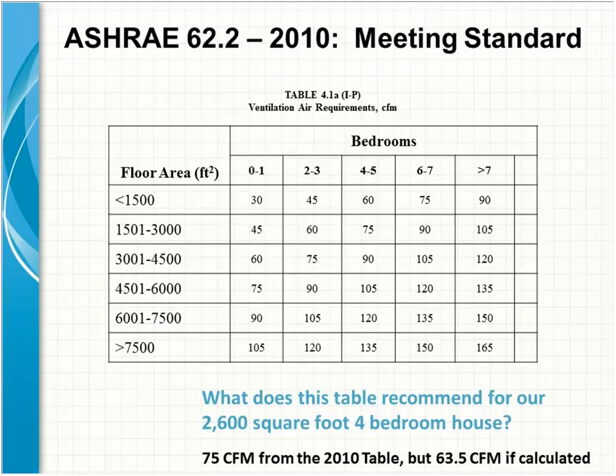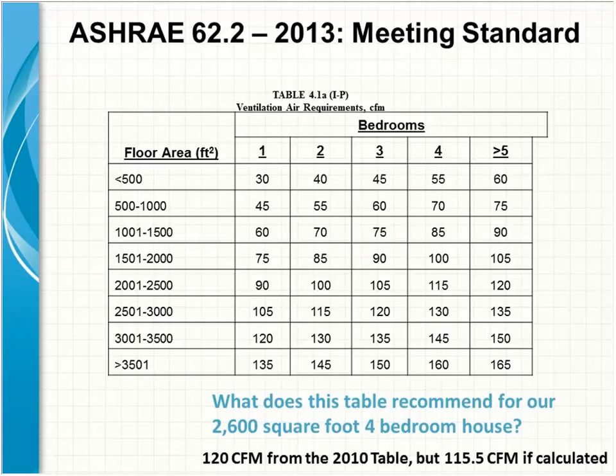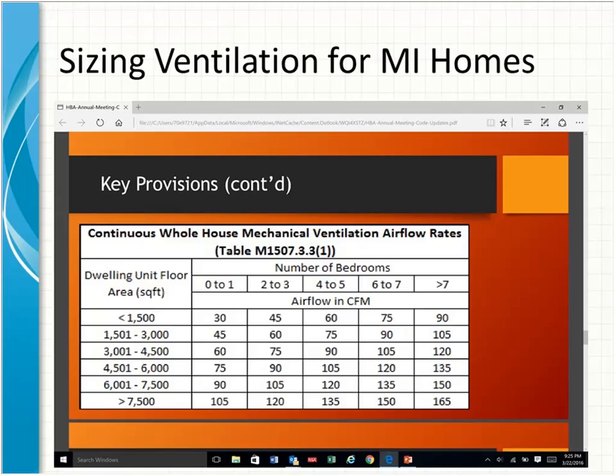If you take a 4 to 5 bedroom, 1,500 to 3,000 square foot home, 2010 version, we need 75 CFM. And if we look at that same home in the 2013 version, let's say in a 4-bedroom at 3,000 square feet, we would need 130 CFM. So it's just an easier way to get there. The number of CFM, I won't say is not the important thing. The important thing is that we're getting some ventilation in the home. And again, I don't know anyone who's using the 2013 version at this point, so mostly we'd be looking at the 2010 version.